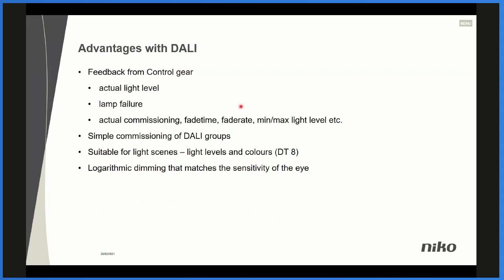So that's the installation part. Furthermore, we can now communicate, or we can get feedback from our control gear. That means we can ask a question to one of the luminaires or to all luminaires. What is your actual light level? A question in DALI is a query light level, and then we have a response. That means we can have feedback from the luminaires to say, okay, this is your light level. And also for maintenance, a facility manager could ask, do I have a lamp failure? And we can say, okay, now this lamp is broken. It has to be replaced.